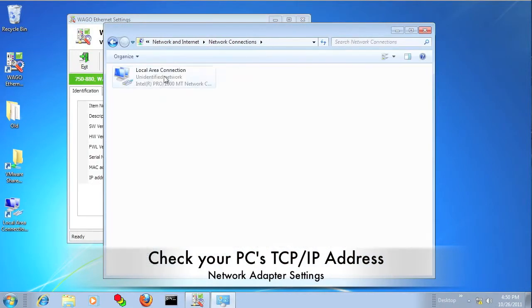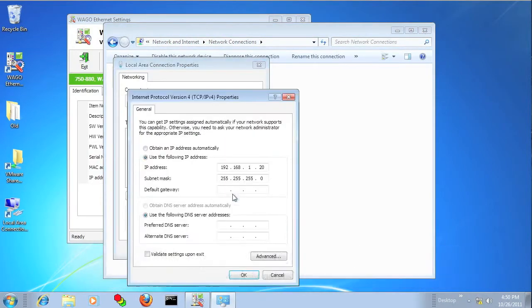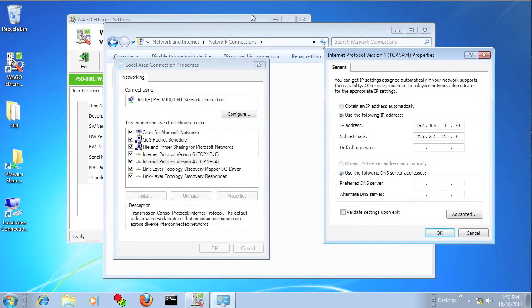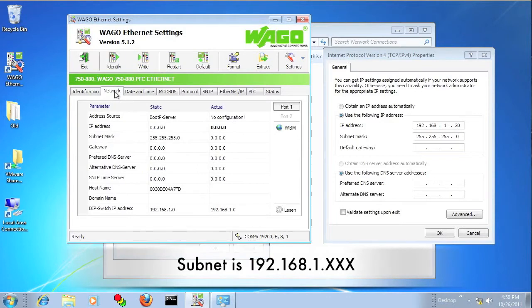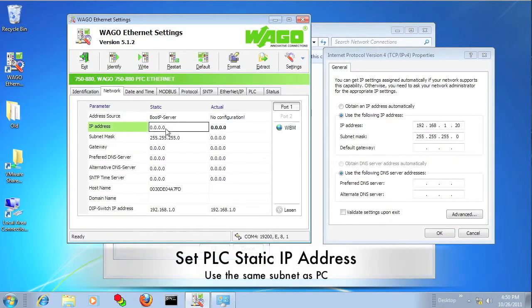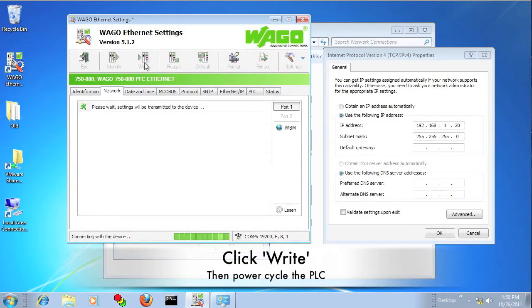Now we want to make sure that we put the PLC on the same subnet as our computer. Going into the network settings, you can identify the IP address that your PC has, and then choose an IP address for the PLC on that same subnet. In this case it's 192.168.1 and we're going to make it .3 for the PLC. Then click the button at the top to apply that change.